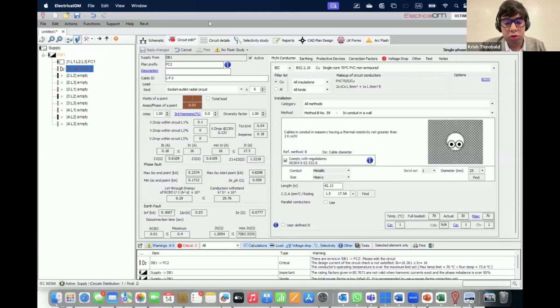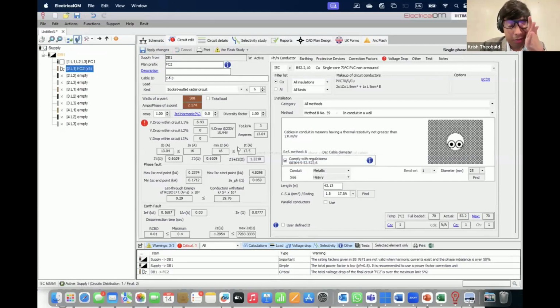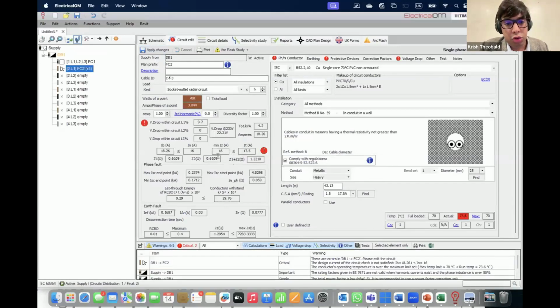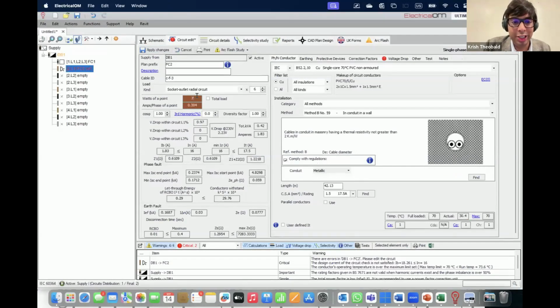So we'll take it as say 500. Yeah, that's not still an issue actually. Even 700 is not an issue. That's just a different warning. I'll show you what I mean. So what it's essentially telling us is that we have a design current of 18.26 amps. There are devices only rated to that much. So if I change this to say 500, I don't have that issue anymore.